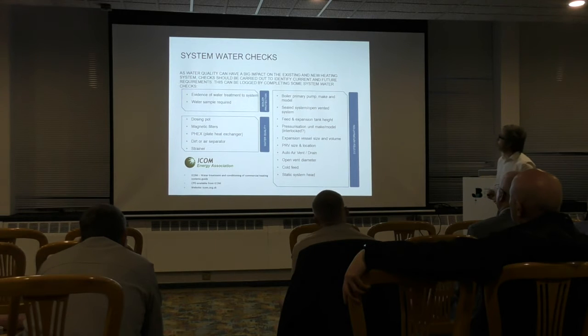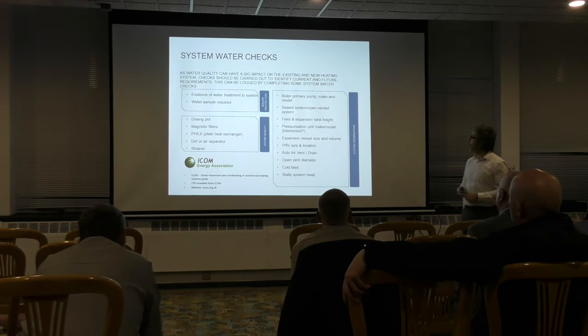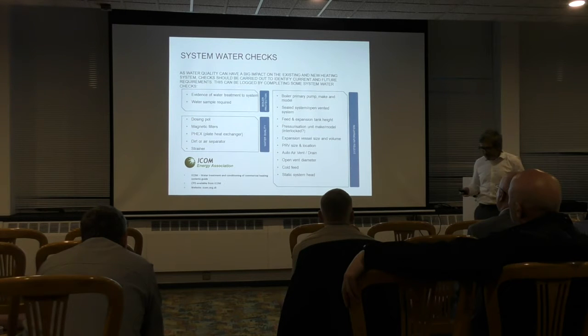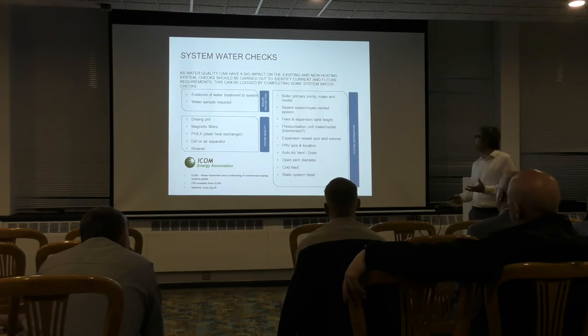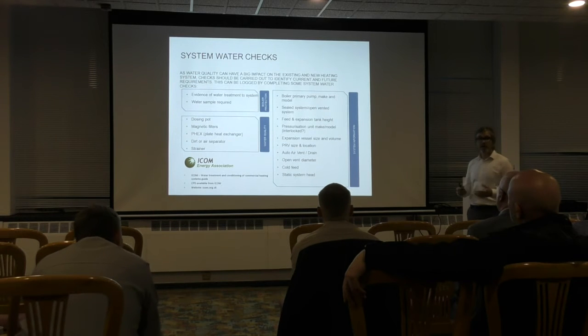But other pointers as well on the side there, we talk about the boiler primary pump, making a note of the make and model of the boiler pumps. Boiler pumps get changed a lot more than actual boilers themselves. So you see it so often that you go into a site and think, well, actually the pumps look good. The boilers are a bit knackered, but the pumps look alright. So it could be that you could utilise those existing pumps. So always make a note of the pumps, so you can get the curve of those pumps and just see if they'll be suitable for your replacement project.